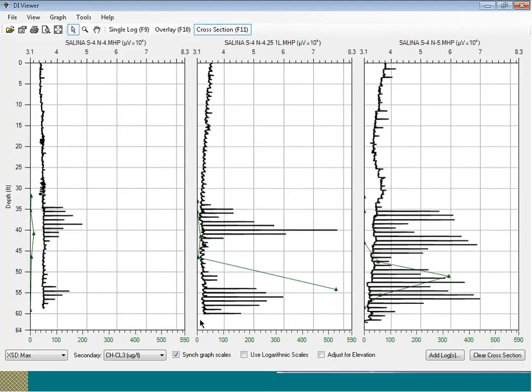I've shown logs run in standard MIP as well as low-level MIP, and I've talked about how we've switched between them. One thing I want to mention is it's very easy with an operator who has a low-level controller, if they run all their gas lines to that, it is literally only 2 lines and 1 union to change between these 2 methods. So literally it is less than a minute that it would take to change between running standard MIP and running low-level MIP.